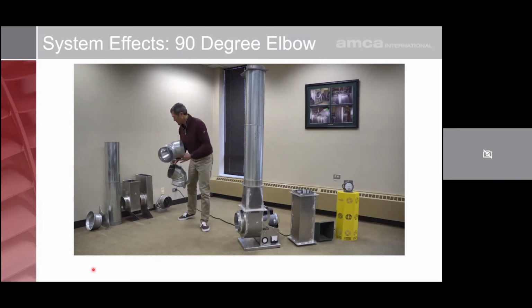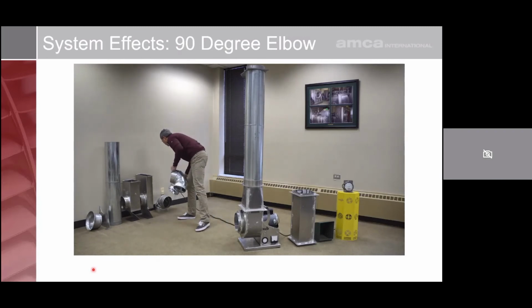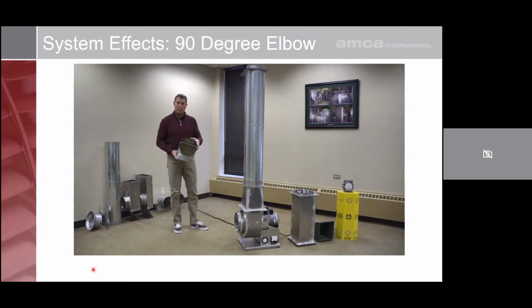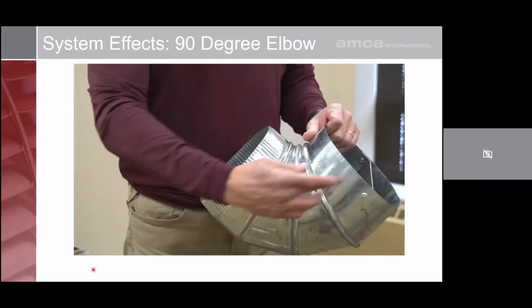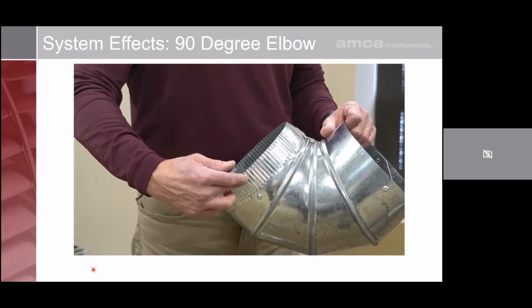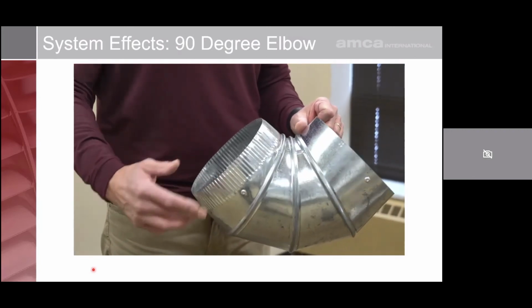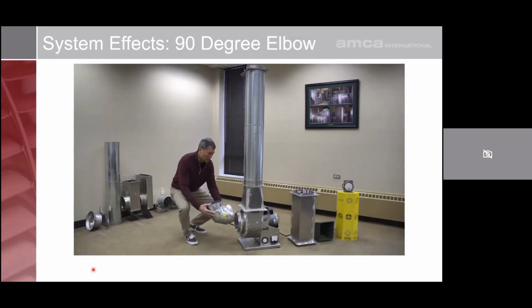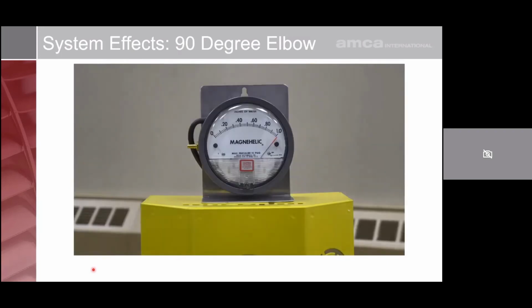Now the next thing we're going to do is take off this one here, and we're going to add an elbow that has a turning vane in it. And that turning vane basically splits the duct into two sections. So when we put it on here, look at the magnehelic, you'll notice that there is still a loss associated. However, that loss is much less than what it would be if we had an elbow with no vanes in it.